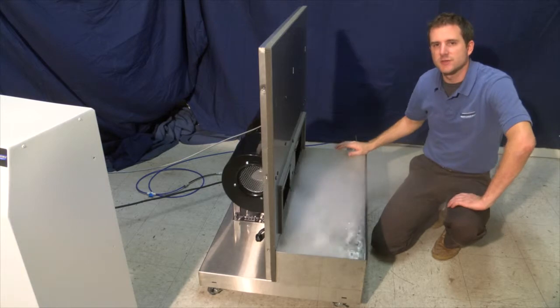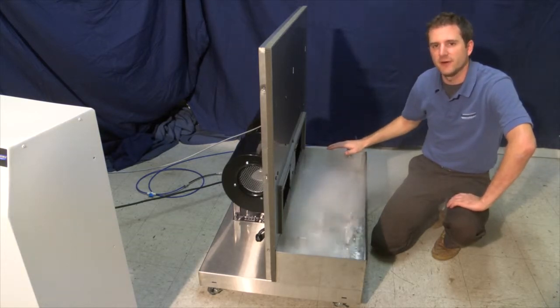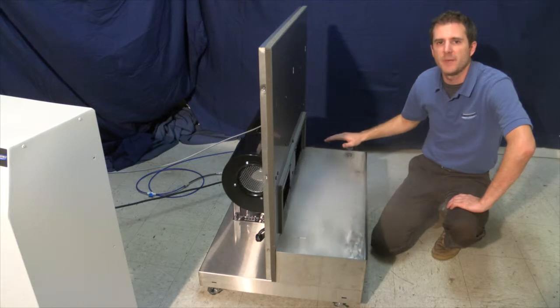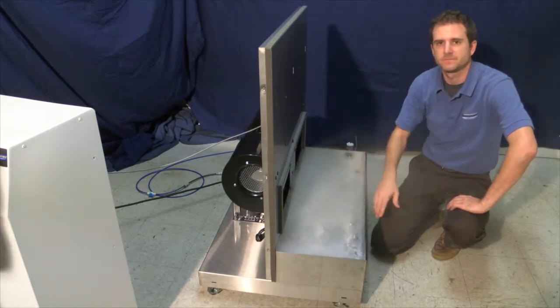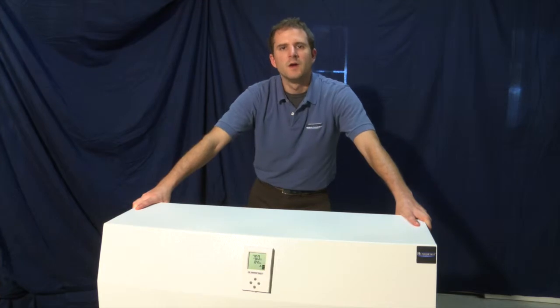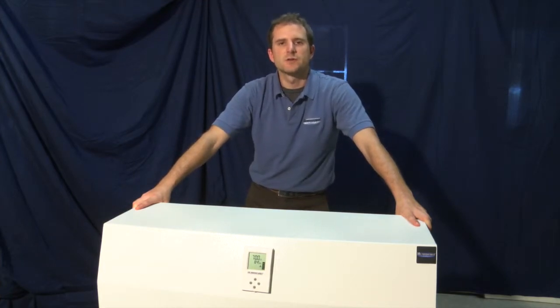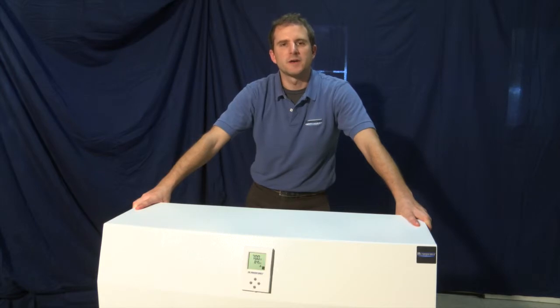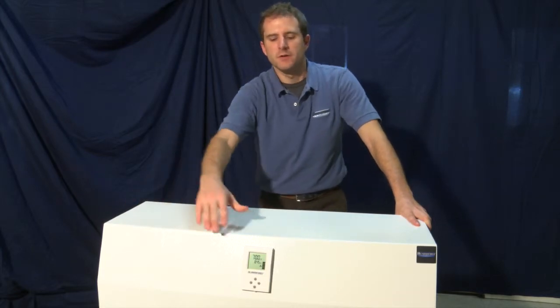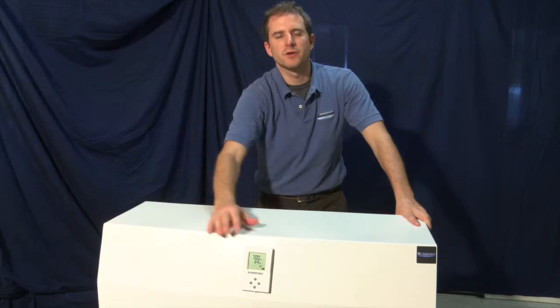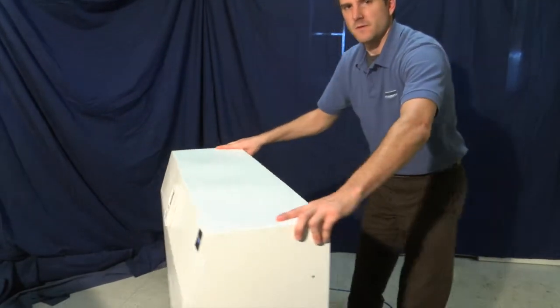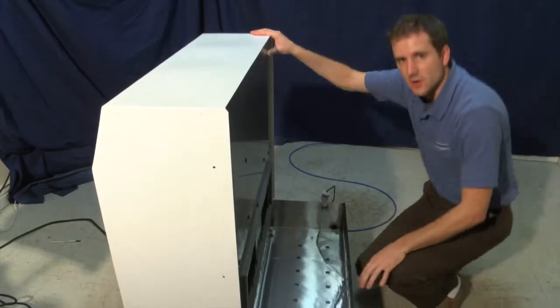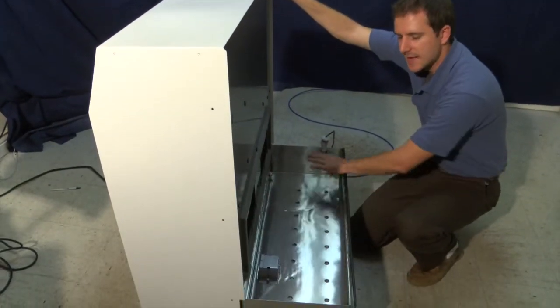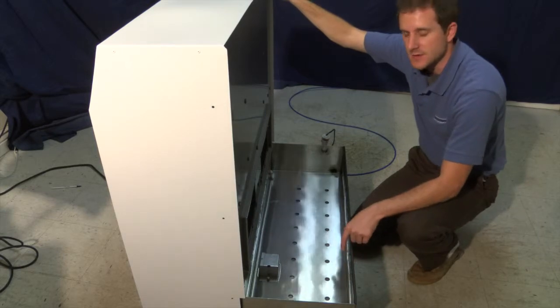Each transducer should have a 2 to 3 inch fountain or finger of water off of it, and the mist would roll off that fountain. All transducers should be operating at the same time in a uniform pattern. Another scenario that can keep the transducers from operating is low water, or not enough water supplied to the humidifier. Note the humidistat is on and calling for humidity, but the transducers are not operating. This is because there's not enough water in the water pan for them to operate safely.